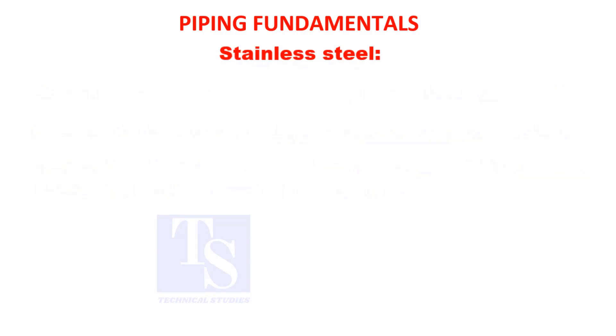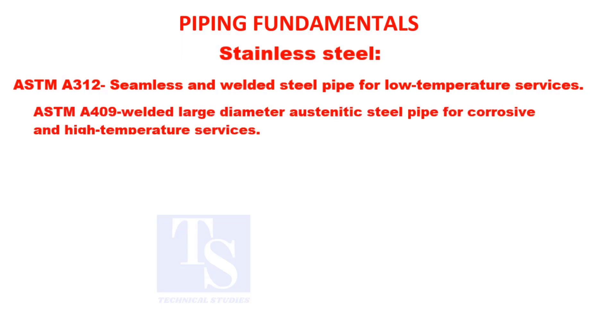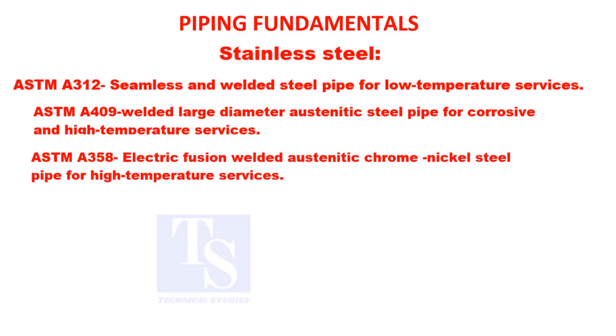Stainless steel ASTM A-312: seamless and welded steel pipe for low temperature services. ASTM A-409: welded, large diameter, austenitic steel pipe for corrosive and high temperature services. ASTM A-358: electric fusion welded austenitic chrome nickel steel pipe for high temperature services.